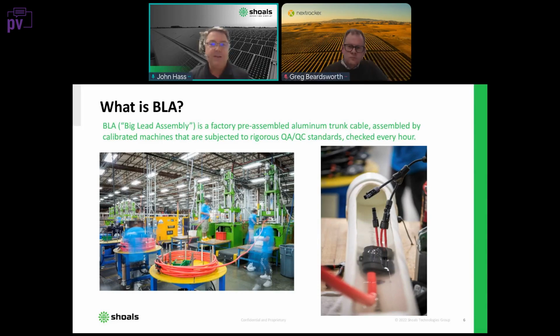Whether it's the mold drop that you see there sitting in the water, or any inline fuse, crosses or tees, anything that is an overmolded component is put through a wet high pot test that guarantees a complete IP68 seal. The UL 9703 standard for which our products are evaluated requires a pass-fail for leakage current during the high pot test of 10 microamps. Our internal standard is 0.5 microamperes. And so we've set our limit 95% lower than the UL 9703 standard, so that when you get the product delivered to the field, it is a completely sealed system. Next slide.